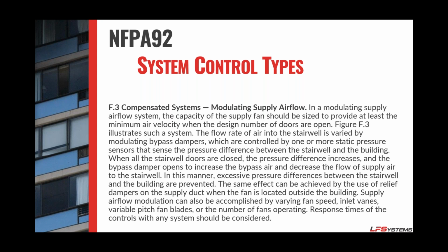So how do we fix this? Well, per NFPA 92, it's interesting. NFPA really digs into stairwell pressurization. There's a very, very small section about elevator hoistway pressurization, but the concept applies to both systems. A modulating supply airflow system will now change the amount of air that's put into the system purely based on pressure. So when doors are closed, there's one volume. Once doors open, we ramp the fan up and change that volume, okay?